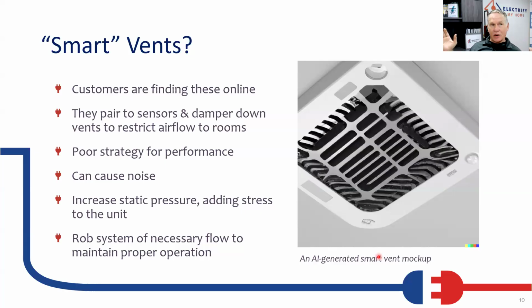If you've already got a system that has high static pressure and you start shutting off registers, that can be the breaking point where that unit is no longer going to work properly and we start wasting a lot of energy and not getting the job done. Sometimes it's just better to keep those rooms conditioned. We'll talk about that for a minute too. Customers are finding these things online, and they can obviously cause noise. Anytime we shut off airflow at the end of the duct, all the air has already gotten there, so it's going to try to sneak through the things, which is another reason why dampers are so much better: they're upline and closer to the system.